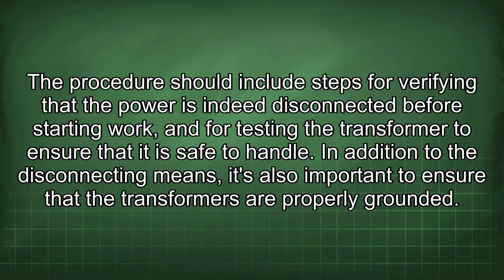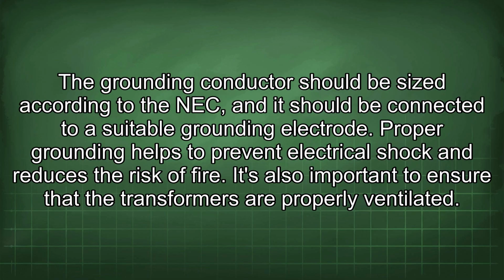In addition to the disconnecting means, it's also important to ensure that the transformers are properly grounded. The grounding conductor should be sized according to the NEC, and it should be connected to a suitable grounding electrode. Proper grounding helps to prevent electrical shock and reduces the risk of fire. It's also important to ensure that the transformers are properly ventilated.